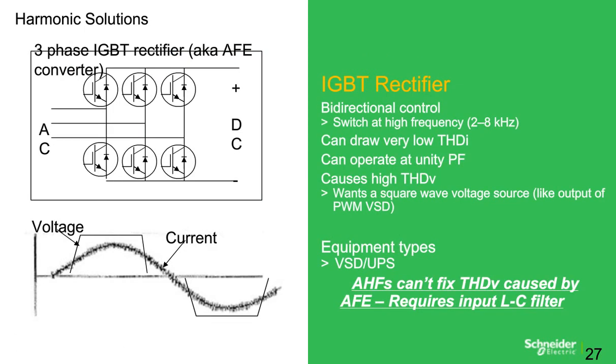So next, we'll move on to a three-phase IGBT rectifier, also known as an active front-end converter. And this is typically the newest design of a rectifier that uses IGBT devices, which are devices that permit current control in both directions, AC to DC and DC to AC. Different control logic can be used to create different levels of current control between the load and AC lines. Two methods primarily in the low harmonic mode of control are used for pump and fan applications, and the active front end does the following.